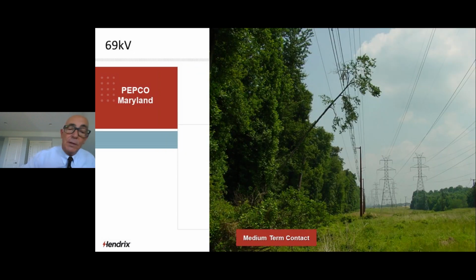There's an interesting photo. Here's a situation where there's another Maryland Pepco transmission line, 69 kV in a right of way. Every 6 months they do a helicopter patrol. The helicopter radioed in: you've got a tree down on your line. The line's out. They said the line is not out. So they sent people out, trouble men. They took photos, cut the tree down. No problem, no damage to the conductors. If that was a bare wire line, it would be on the ground, and the underbuild would also be on the ground. So that was up there somewhere between 1 day and 6 months, probably somewhere in between that.